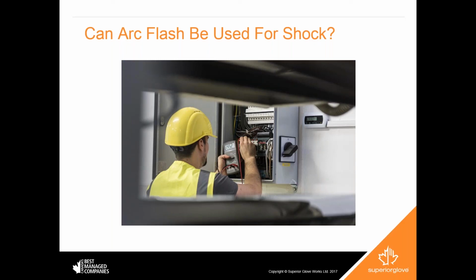Another question we have here is whether your typical home electrical panel is going to be at risk for an arc flash. Yeah, so basically what OSHA, the regulations, what they mandate is that any equipment operating over 50 volts or higher needs to be tested for the arc flash hazard. So if you have something that's over 50, it used to be, the misconception was that if it was under 240 volts, an arc flash wasn't possible, but it's not the case. So any equipment you're operating over 50 volts, chances are it needs to be tested for arc flash. It's a lot harder in those low voltage areas for an arc flash to be sustained, but over 50 volts, it needs to be tested.